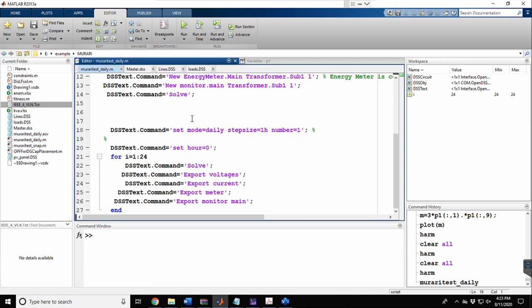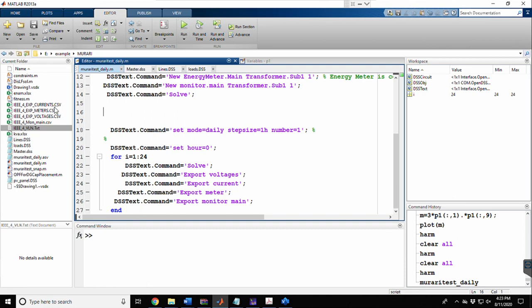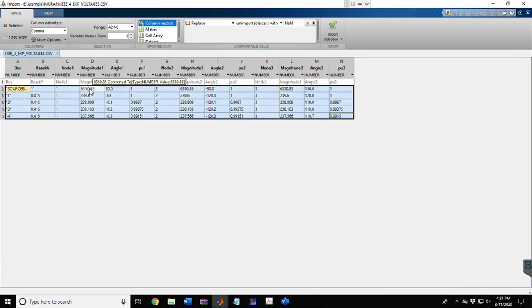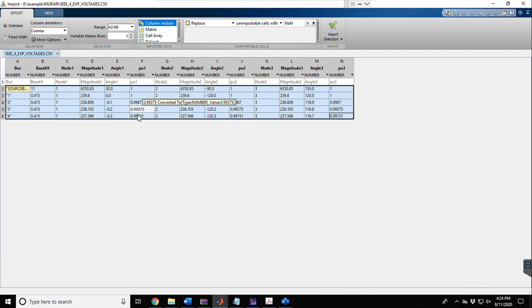The program has run and we have exported four CSV files. Looking at the voltages file: at the source bus the base kV is 11 kV (line voltages), and for buses 1 through 4, due to the transformation ratio, the base kV has changed to 0.415 kV. Column D shows the magnitude of the actual phase voltage, which reduces along the radial network, along with the phase angles. Converting to per unit gives the per-unit voltage.